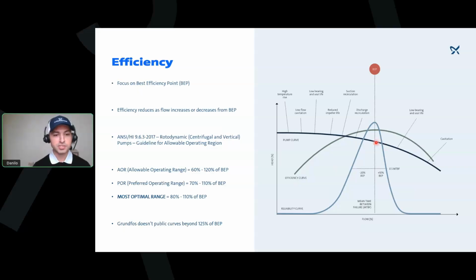As you see in this curve here, it looks pretty much in the middle, but manufacturers can do the following: if your selection is right here, at the right-hand end, I can extend that line, and all of a sudden your selection looks like it's in the middle. So always make sure you're at the highest efficiency possible for that duty condition. Now we're going to talk about running your pump outside of that region, and that is because in a few slides we're going to talk about part load conditions.